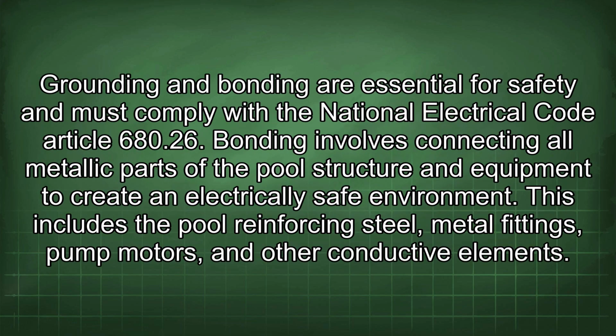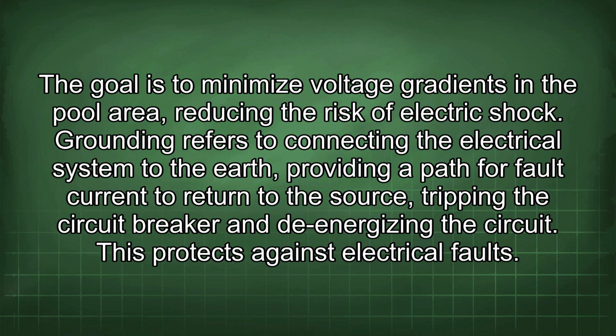Grounding and bonding are essential for safety and must comply with the National Electrical Code Article 680.26. Bonding involves connecting all metallic parts of the pool structure and equipment to create an electrically safe environment. This includes the pool reinforcing steel, metal fittings, pump motors, and other conductive elements. The goal is to minimize voltage gradients in the pool area, reducing the risk of electric shock.